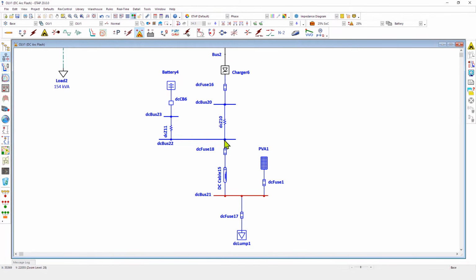It calculates the short circuit contributions through various sources in the circuit and utilizes the characteristic curves or the protection characteristics for fuses, breakers, and so on to determine the clearing time of the arcing current. So let's go ahead and run our DC arc flash simulation and observe the incident energy as well as the fault clearing time. Notice that the incident energy is 0.182 and the clearing time is 0.01 seconds. You will also observe that the short circuit current from battery 4 is less than what we observe from DC short circuit, because what we are showing here is in fact the arcing current and not the bolted fault or zero impedance fault current.